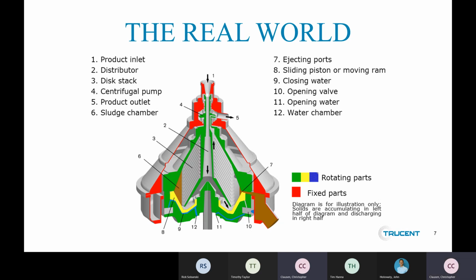On the left-hand side, the brown area is our solid, let's say yeast, which is then expelled into a chamber along the centrifuge housing and dropped either into a bucket if done manually, or pumped out to a storage bin that may go to a farmer for further processing. It can be put somewhere other than down the drain, so you have less wastewater load.